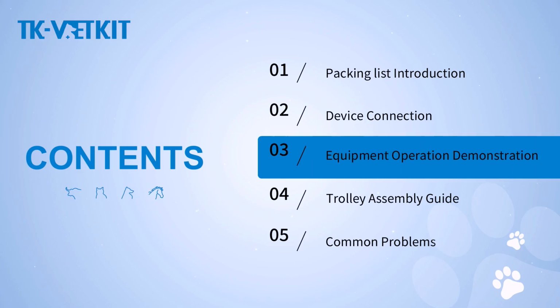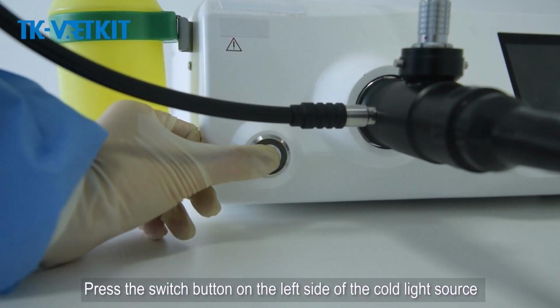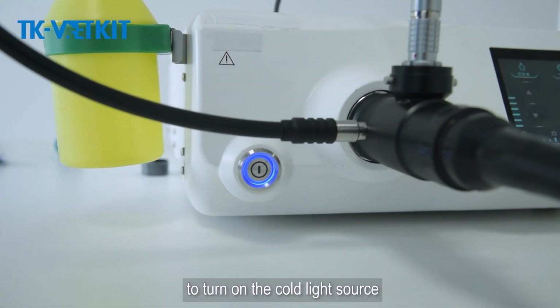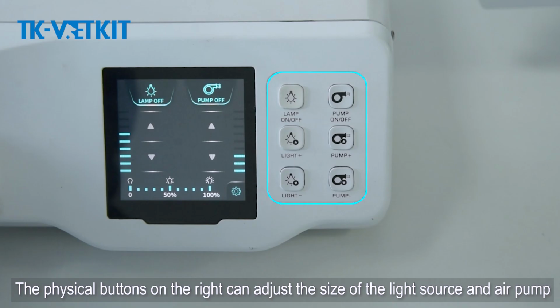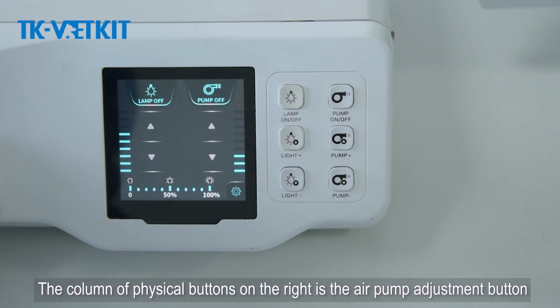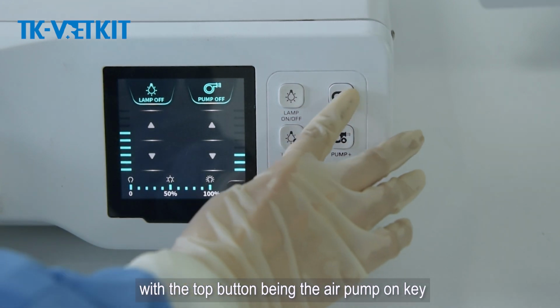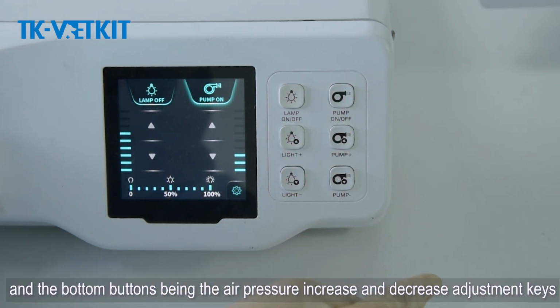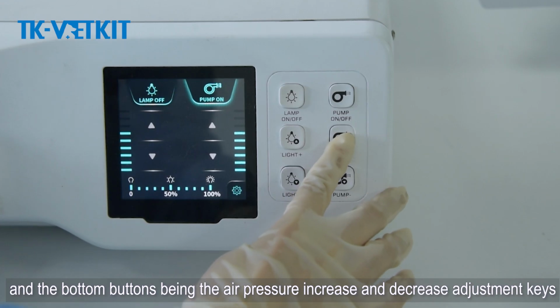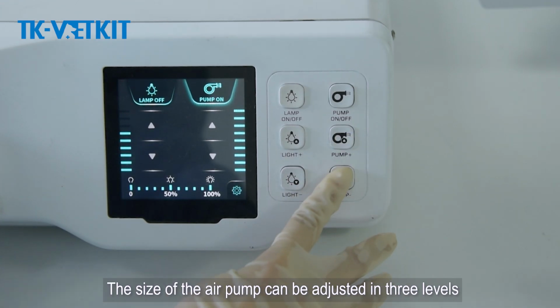Equipment operation demonstration. Press the switch button on the left side of the cold light source to turn on the cold light source. The physical buttons on the right can adjust the size of the light source and air pump. The column of physical buttons on the right is the air pump adjustment button, with the top button being the air pump on key, and the bottom buttons being the air pressure increase and decrease adjustment keys. The size of the air pump can be adjusted in 3 levels.